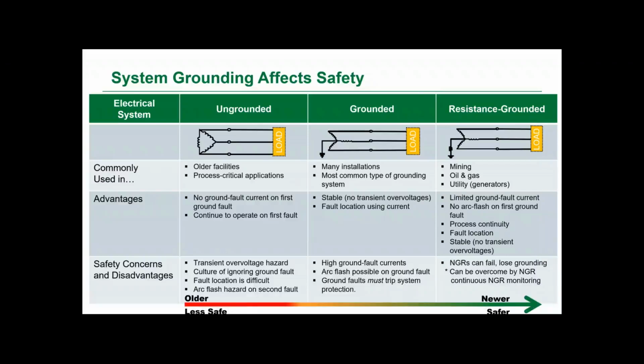advantages I'll get to in a minute, but one thing relating to solidly grounded systems in particular is that fault currents can be quite high. And what that results in is rapid shutdown when there is a fault, and there can be a risk of an arc flash when you have that ground fault. So if you remember that a ground fault is the most common type of electrical fault, you can see that there still is some disadvantage there, just given that that first ground fault could be an arc fault.